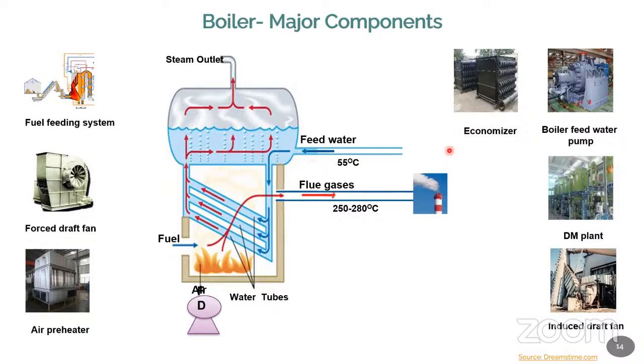Number one. Number two, when you take the condensate water, that water pipe should also be insulated. That's another important point. I saw recently one industry in Udmalpet where they have 100% condensate recovery. But the only thing is, in some places they do not have insulation, especially for the bends and crosses. Actually, they had insulation, but it was worn out and they didn't replace it. When the insulation is not there, automatically what will happen? The temperature will go out, as in any normal pipe. That will reduce my feed water temperature. So the condensate pipe should also be insulated, and the energy loss, temperature loss, should be as minimum as possible.